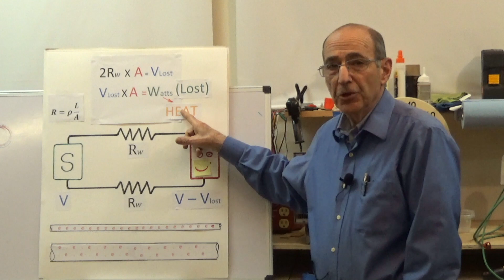You also know that volts times amps equals power in watts. So if I'm losing this much voltage and I have that many amps flowing through the circuit, then the voltage lost times the amps equals the wattage that's lost. Where does that wattage go? It goes into heat. So you see, we have two issues with real wires that have resistance: they cause a loss of voltage - we call that voltage drop in the industry - and we're generating heat.